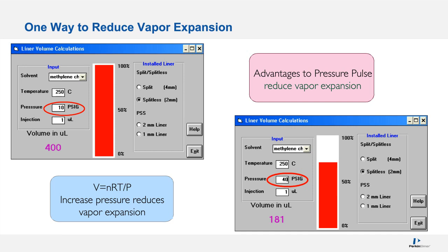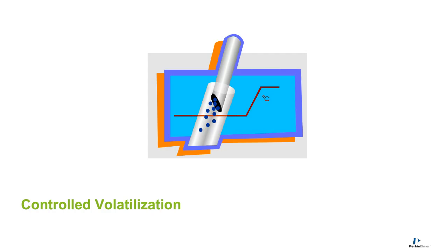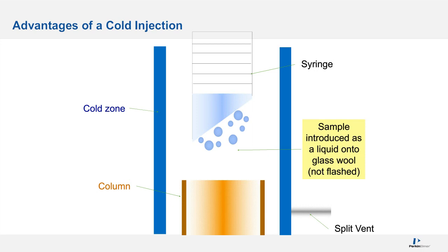Another way to do that is to do controlled volatilization. We could do solvent purge, we could do split, we could do splitless. There's a lot of options here. But in trace level analysis, which is what we're talking about now, we're going to do a splitless injection. So we inject our sample as a liquid, and we could purge out the solvent because the injector's cold here. So we could do 50 microliters without backflash. Since the injector is cold, we're not going to get backflash. The sample is injected as a liquid and stays in the injector port, and then the solvent gradually dissipates depending upon what your initial temperature is.